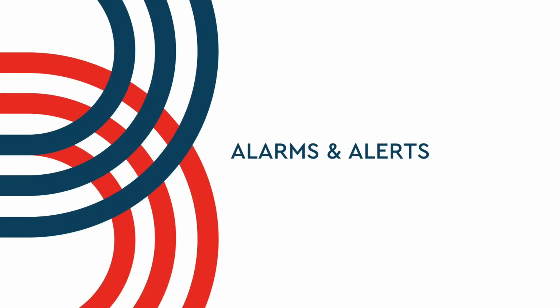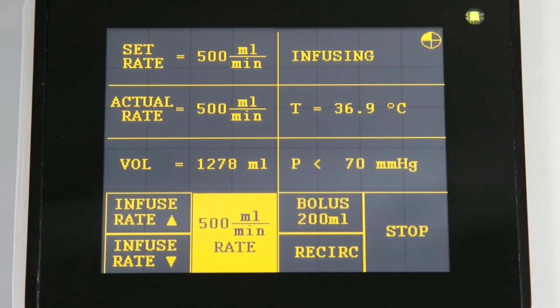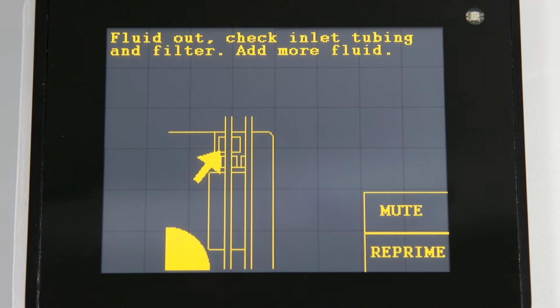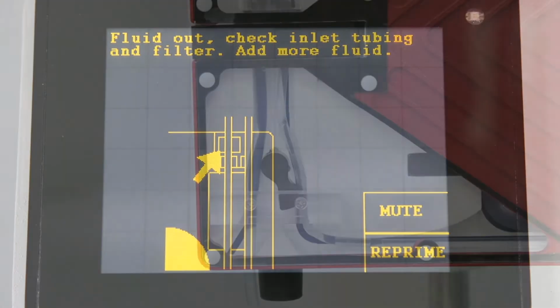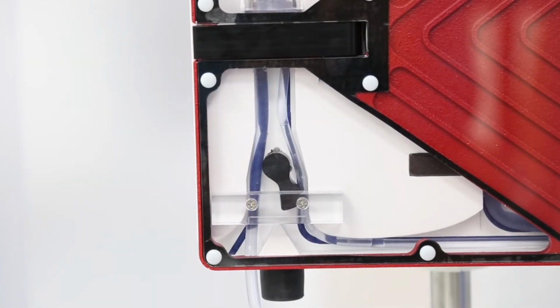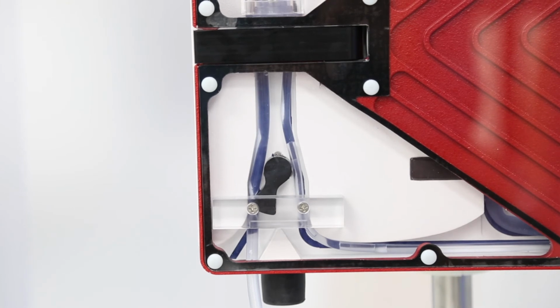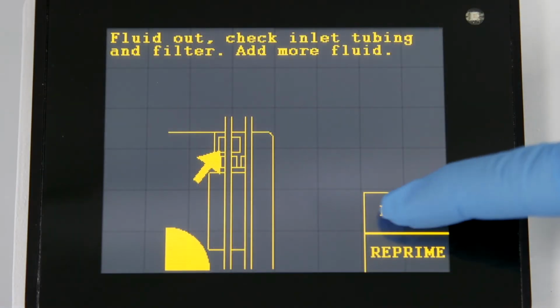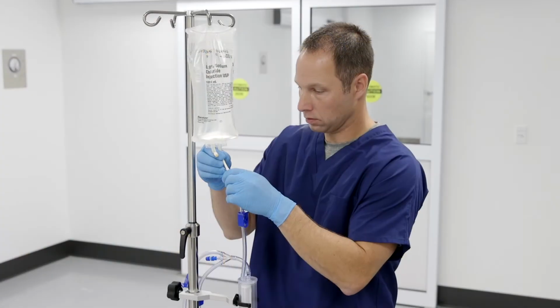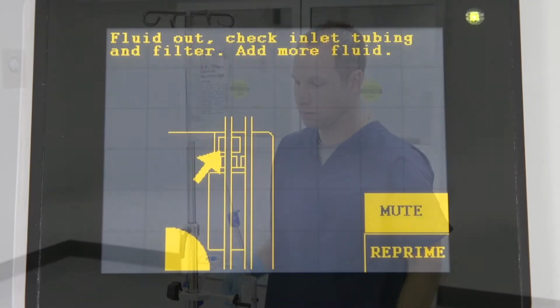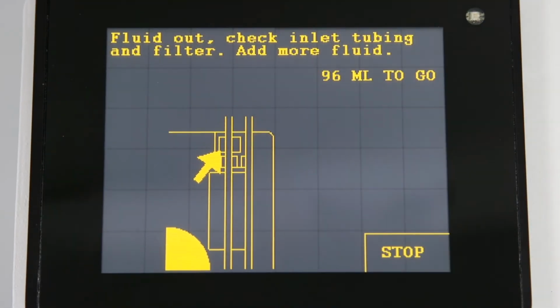Here are some troubleshooting tips for the alarms you might experience. A fluid out alarm will occur if the operator allows the system to run out of fluid. The Belmont will immediately stop infusion and automatically clamp off the patient line. Press mute to silence the alarm, add fluids, and press reprime. The system will automatically reprime in 13 seconds.